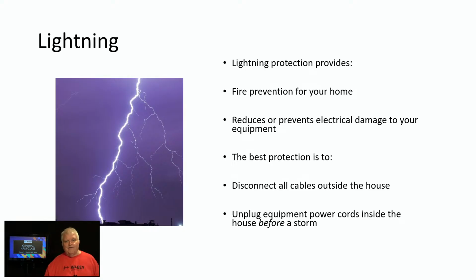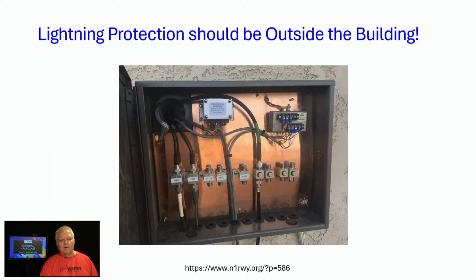The best defense is to pull cables off of your equipment, the power cables or antenna cables, if you can do that before a storm occurs. Now, if you can't do that, or it's a site that you need to keep up all the time, then surge arresters mounted in a controlled environment like this panel with this grounded copper plate on the back.